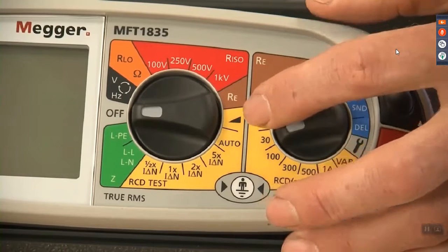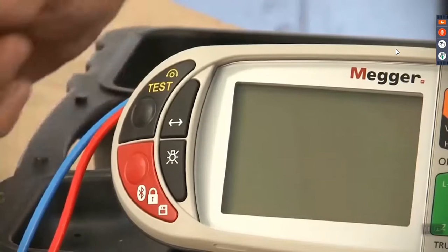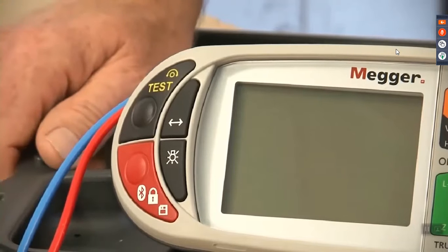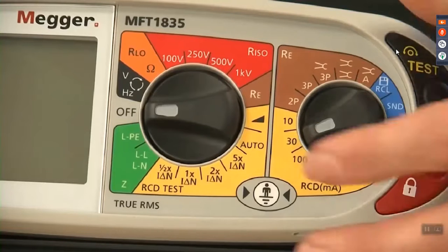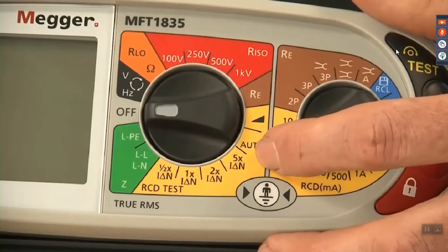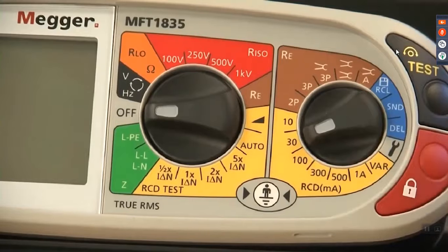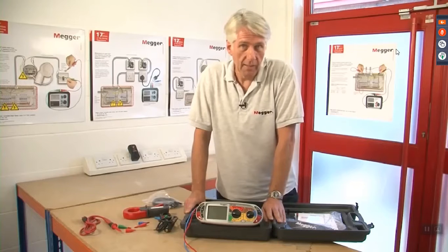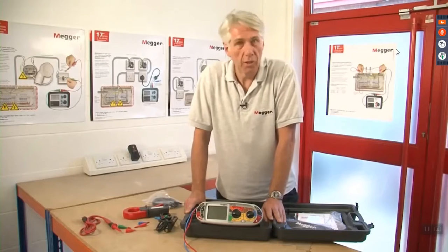For fault investigation where there's nuisance tripping, the tester also has a ramp test, which can find the actual tripping point of an RCD. We can also switch between 0 and 180 degrees. Finally, if you're working alone, you can use the auto test feature to undertake the tests on the RCD. All you have to do is stand by the RCD and reset it as needed, and then when the test is finished, just look through the results.